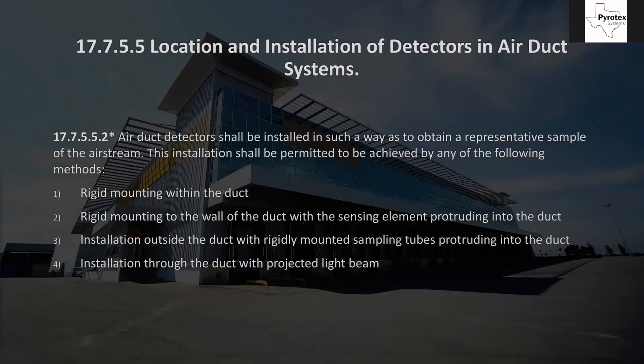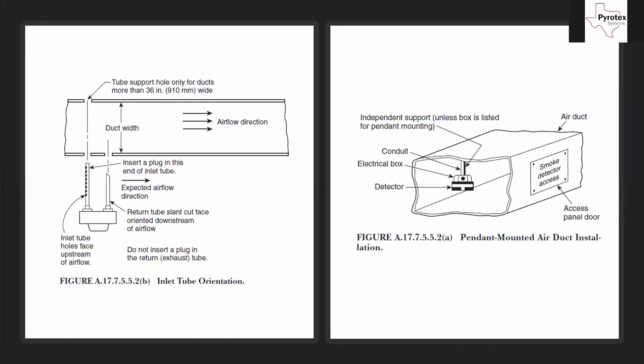Mounting to the wall of the duct with the sensing element protruding is similar to mounting to a ceiling or wall of a building — just now it's the ceiling or wall of the duct. Another method is installation outside the duct with rigidly mounted sampling tubes protruding into the duct — this is the way we usually do it, as it's the most straightforward, easiest to service. The last method is installation through the duct with a projected light beam — essentially a beam detector inside a duct.